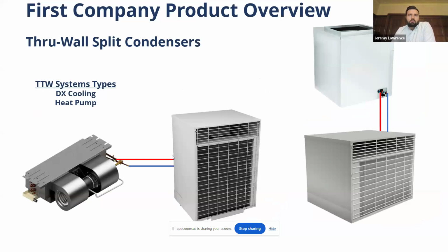These systems that we've talked about so far are all split systems. They do require installation to connect a condenser to the evaporator on site. First Company only makes one specific style of condensers, and that is a through-the-wall condenser. So it is essentially half a PTAC. It sits in a sleeve in the wall and exchanges outside air through the condenser, and then is connected via line set refrigeration pipes to the indoor fan coil. And those can be in just about any configuration. The through-the-wall split condensers do come in air conditioning and heat pump systems.